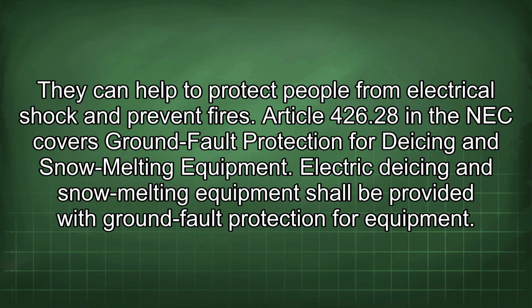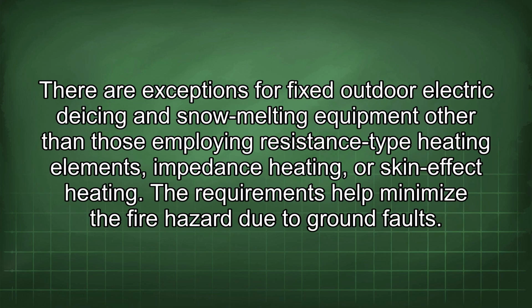Electric de-icing and snow melting equipment shall be provided with ground fault protection for equipment. There are exceptions for fixed outdoor electric de-icing and snow melting equipment other than those employing resistance type heating elements, impedance heating, or skin effect heating. The requirements help minimize the fire hazard due to ground faults.